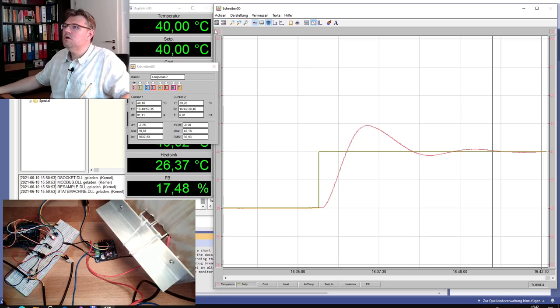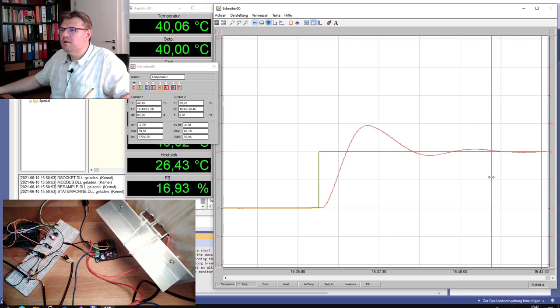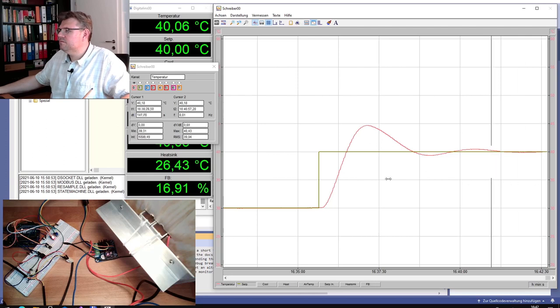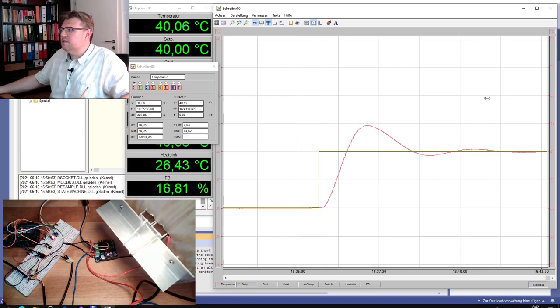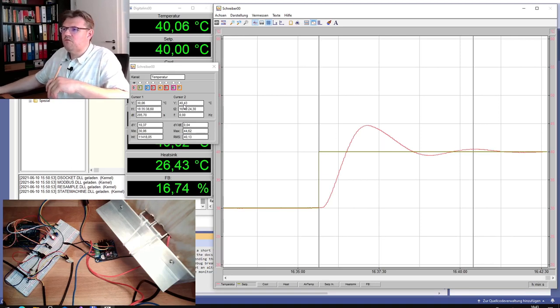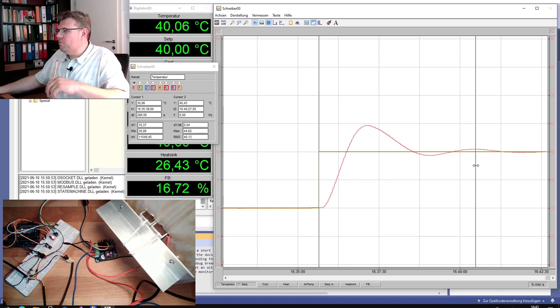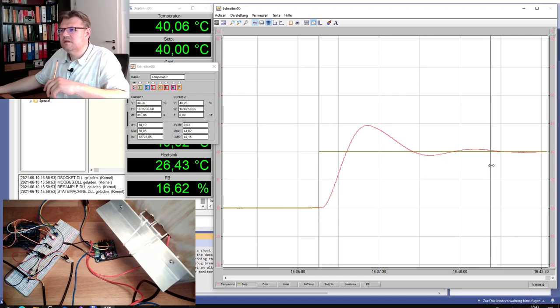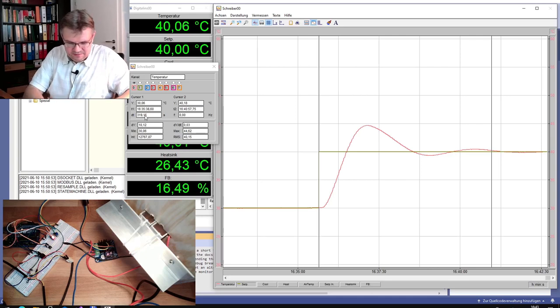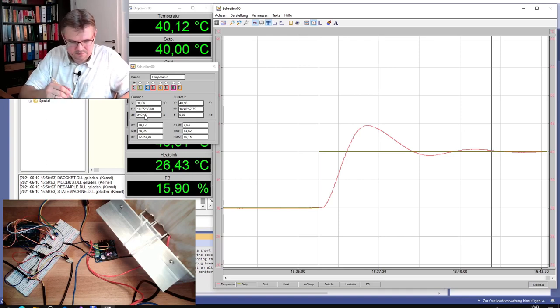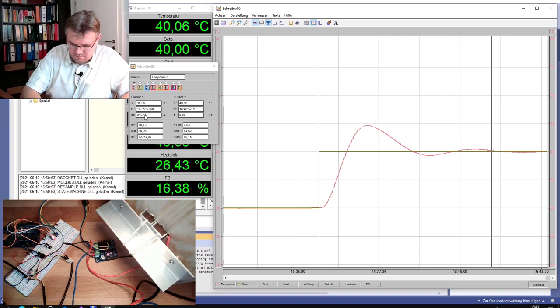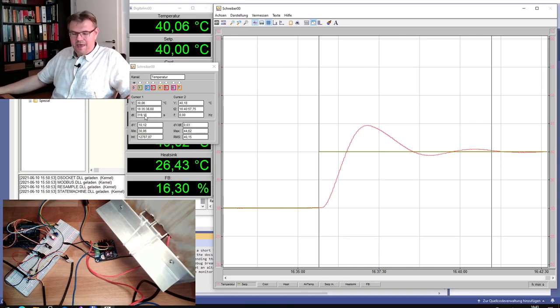So, I will stop this again now. We have to find the point here where we are dropping below. Here. Move this to the beginning. So, here you see cursor 2. That's the right hand cursor. The actual value here where the position of the cursor is 40.43. And now I'm moving this to the right until I am below 40.2 and this is here. Here. So, this is the settling time. The settling time is 320 seconds. Now we have it. Now we have it. All our quality criteria.